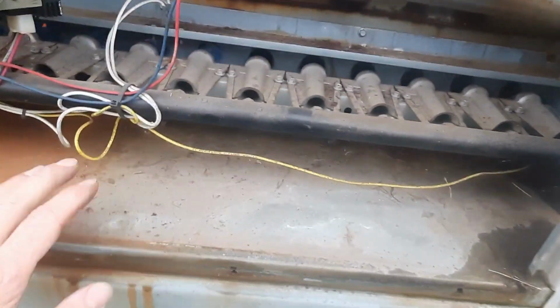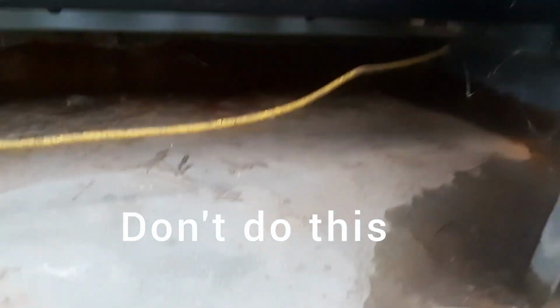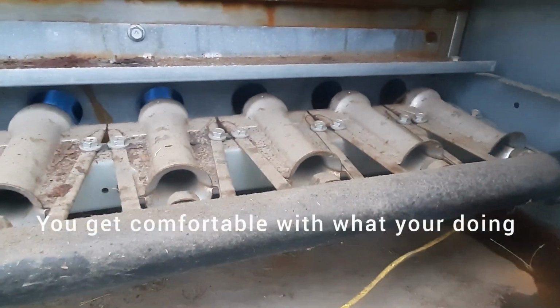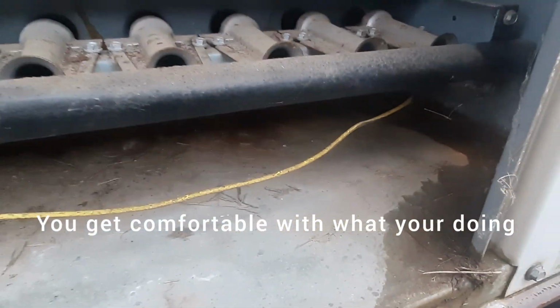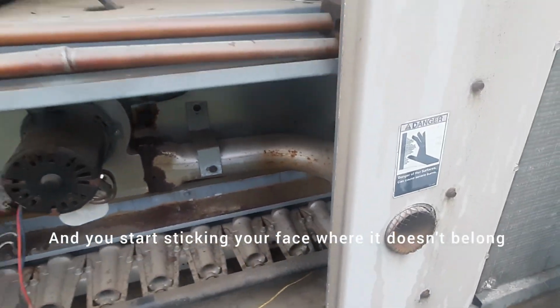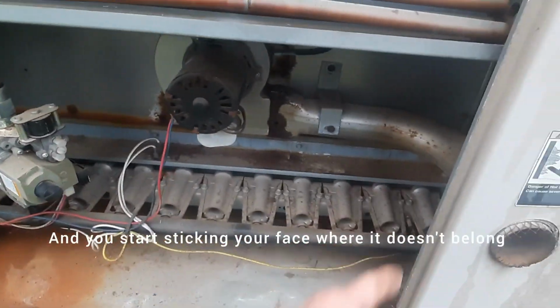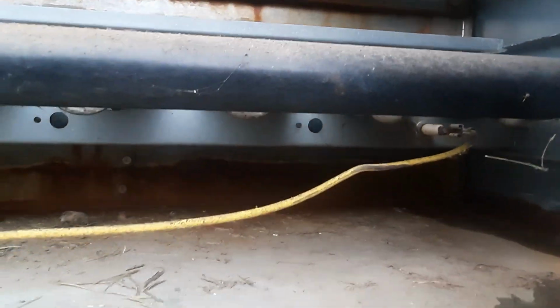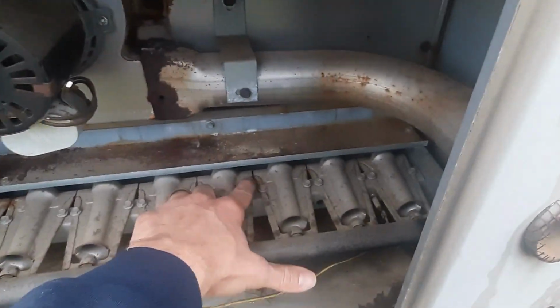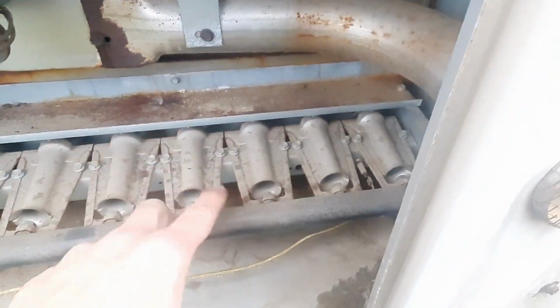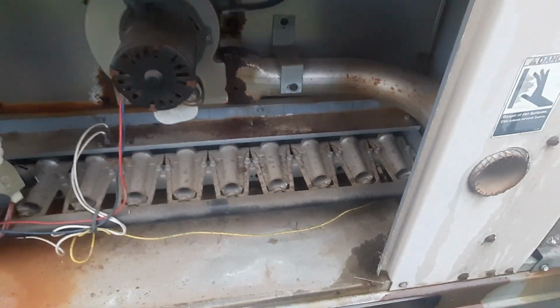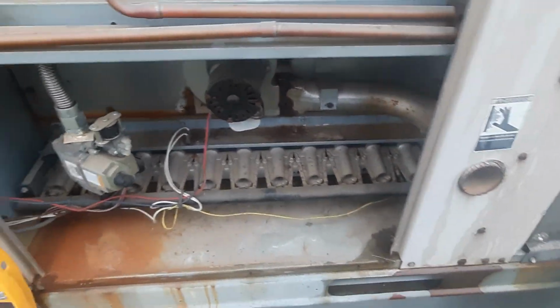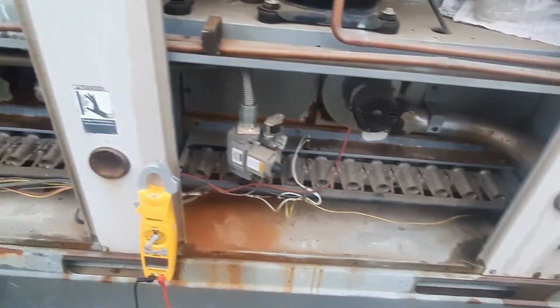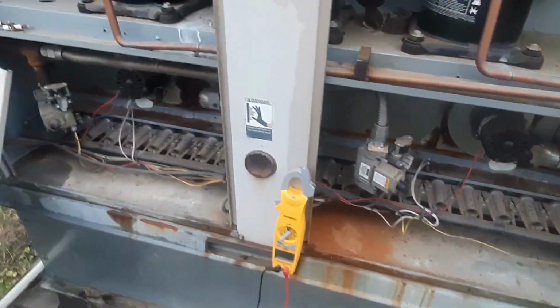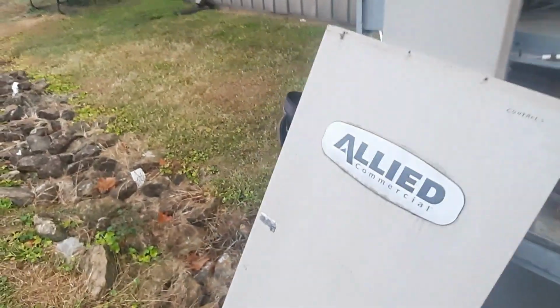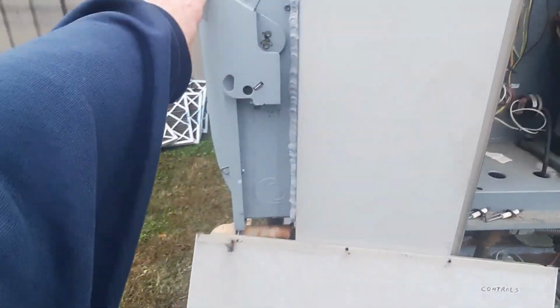Yeah, they're rated 0.55. It's dirty. Those last couple burners out, something blocking either the crossover tube or the burner itself. It just stopped right there. It's weird because this one was running when I got to it. That one's running alright. Let's get this fixed, get this one fired, and then we'll get our temp rise with both of them running.